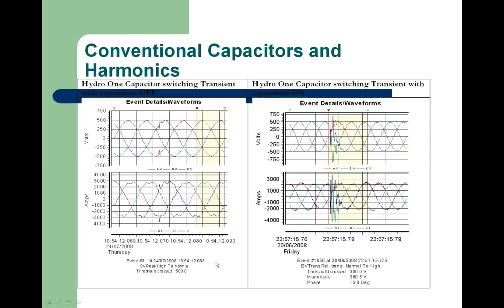I think we're getting closer to the end. I'll try and speed this up a bit. This is on the left-hand side over here. We have a utility capacitor switching event. Utility switch capacitors on, high voltage capacitors on and off to reduce the current, just like we showed earlier that we could reduce the current on a line by putting capacitors. They do the same, and they reduce the current on their transmission lines, which also results in a voltage increase. So they do it on a combination of reducing the current on their lines and increasing the voltage when required, particularly in the summertime when the air conditioning is loaded.